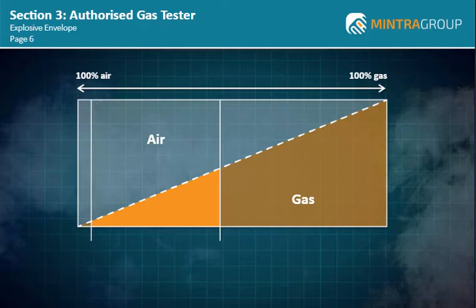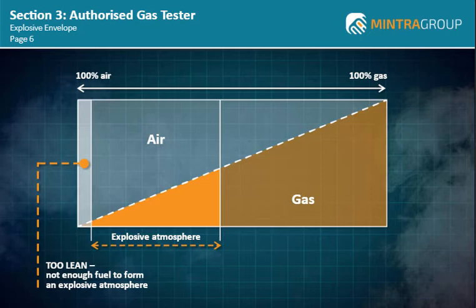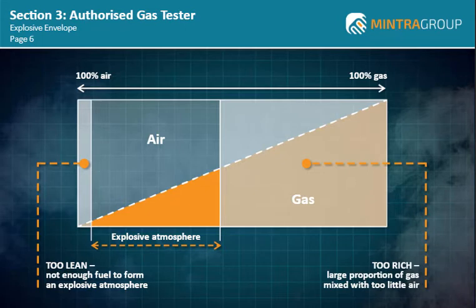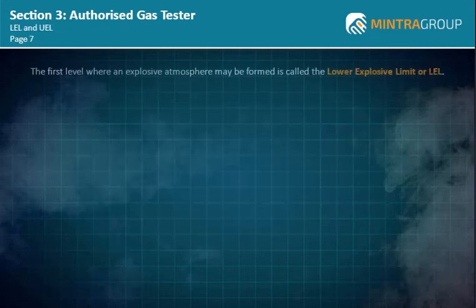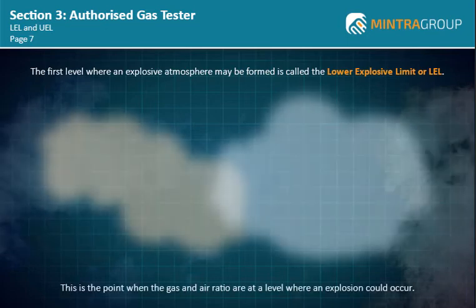When gas and air are mixed in a certain ratio, they can form an explosive atmosphere. If there is too much air, the gas and air mix will be too lean, as there will not be enough fuel to form an explosive atmosphere. However, if there is a large proportion of gas mixed with too little air, this is considered too rich and again will not form an explosive atmosphere. The first level where an explosive atmosphere may be formed is called the Lower Explosive Limit, or LEL — this is the point when the gas and air ratio are at a level where an explosion could occur.